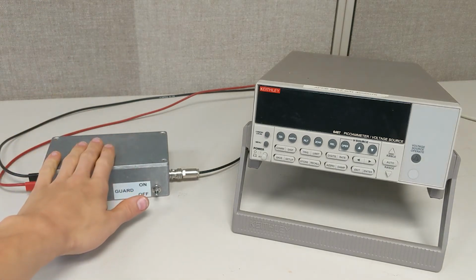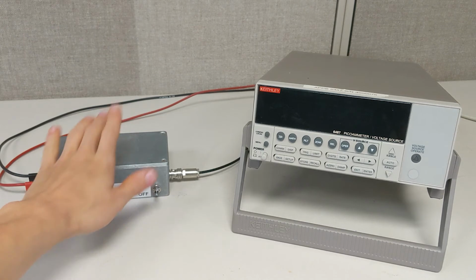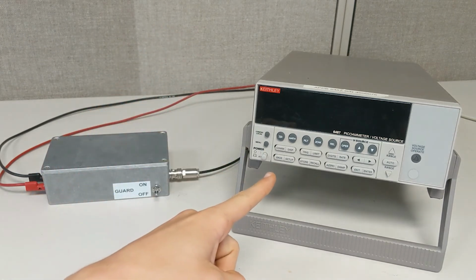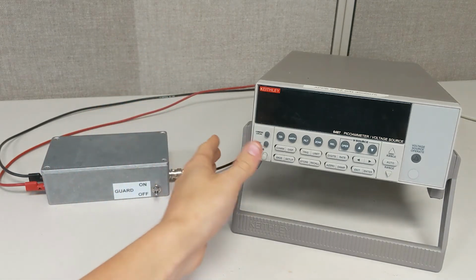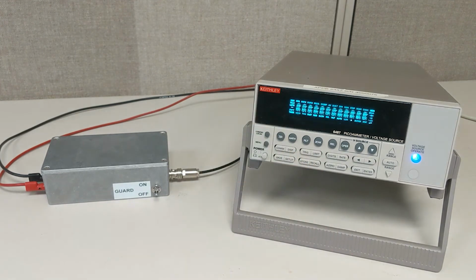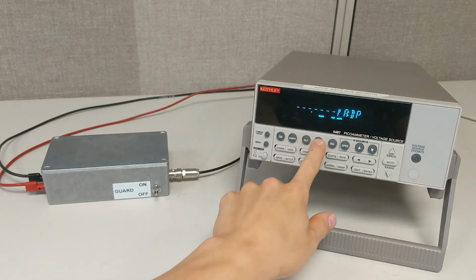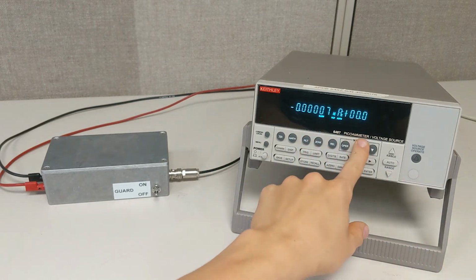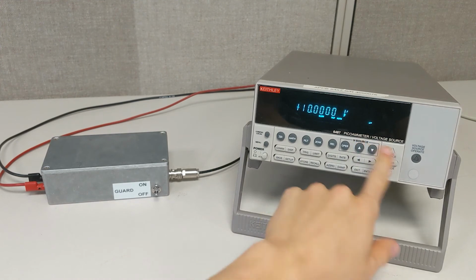In front of me is a physical version of the guard box we have previously explored, now connected to a Keithley 6487 picoammeter to source a voltage and measure resistance. Turning on the 6487, we will first zero out the instrument and set the voltage. For the purposes of our demonstration today, we will set the source to 10 volts.